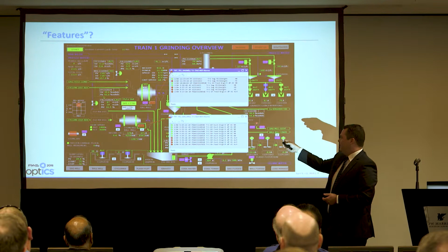Or you could click another button and see only the alarms for the ball mill, because we really cared about those. Then someone would need another alarm, and we'd say, how do we make the operator use it? Let's use the operator guide feature, let's use the reminder for operators. So this comes up - hey, all those alarms you've ignored, now this one comes up in the center of your screen, and you have to acknowledge it.